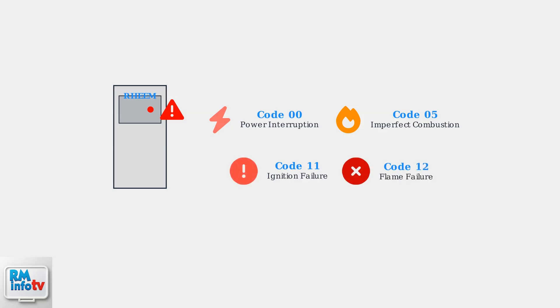Here are some of the most common error codes you might encounter. Code 00 indicates a power interruption or power supply problem. Code 11 means ignition failure, while code 12 indicates flame failure during operation. These are critical safety-related issues. More recent Rheem models feature digital display panels that show error codes directly, making diagnosis much easier than counting blinks.